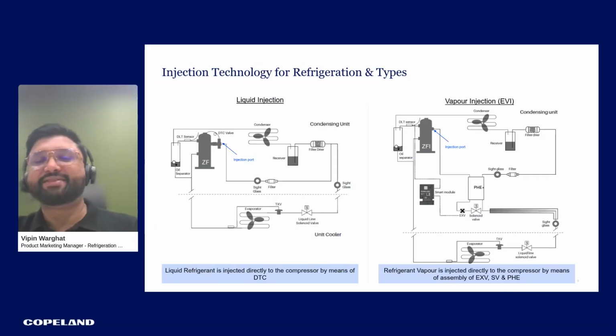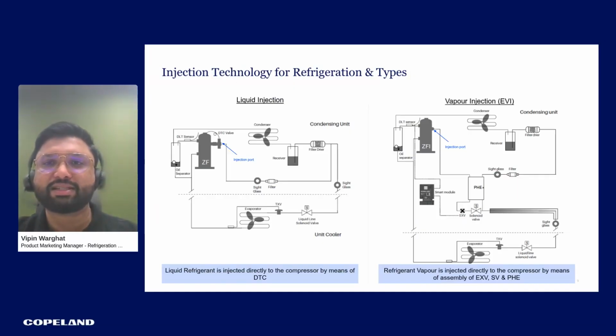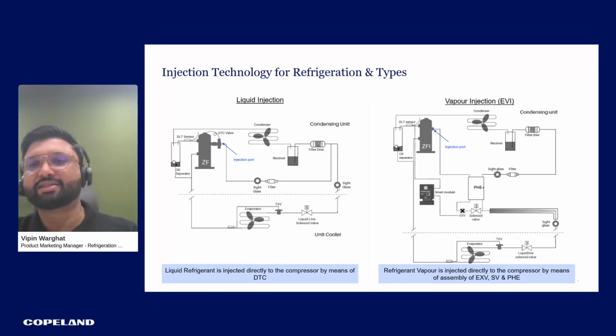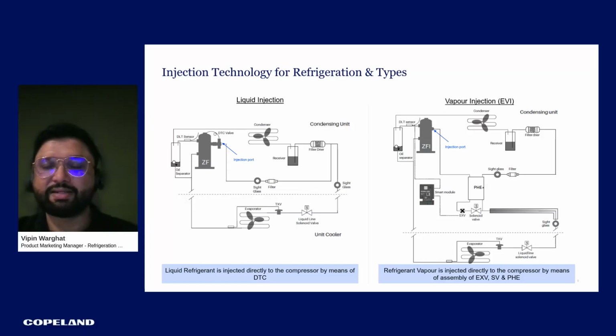Yeah. So specifically for low temperature, there is injection technology in scroll, which is of two types, liquid and vapor injection. Liquid injection is where the liquid refrigerant is injected inside the scroll by means of a DTC valve. While vapor injection is a complex assembly which requires a control module and a PHE, and by expanding the liquid refrigerant through the liquid refrigerant line, the vapor is charged inside the scroll compressor. So that's how vapor injection works. This is the fundamental difference between liquid and vapor injection.